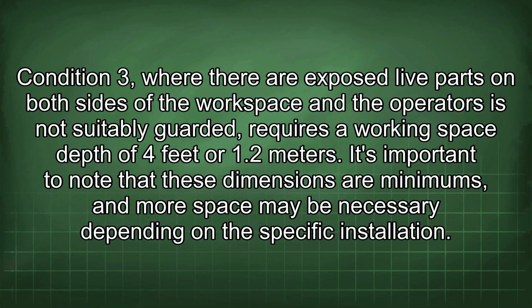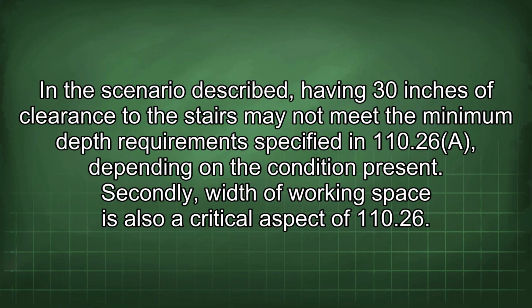It's important to note that these dimensions are minimums, and more space may be necessary depending on the specific installation. In the scenario described, having 30 inches of clearance to the stairs may not meet the minimum depth requirement specified in 110.26a, depending on the condition present.